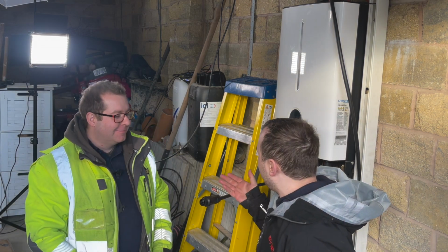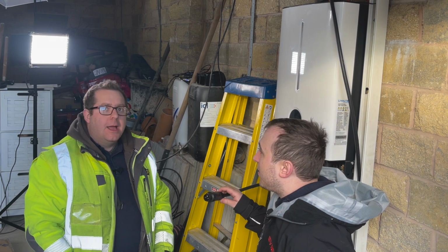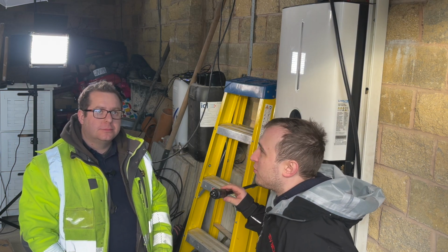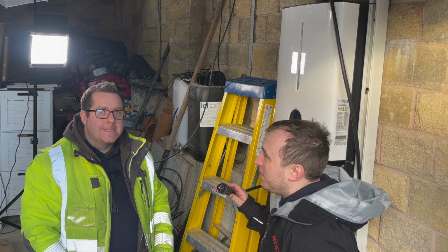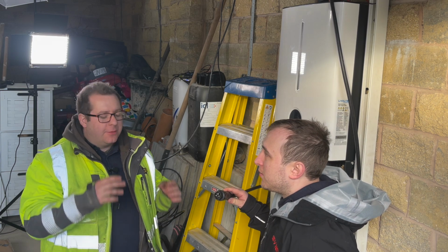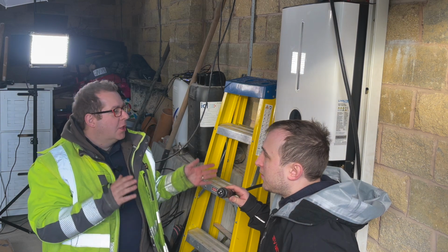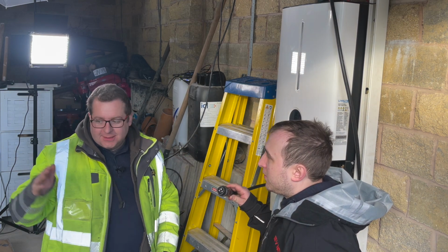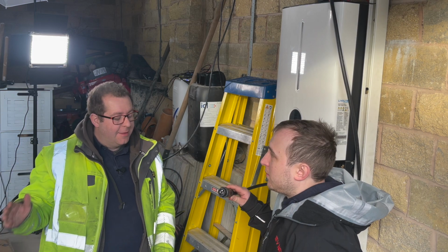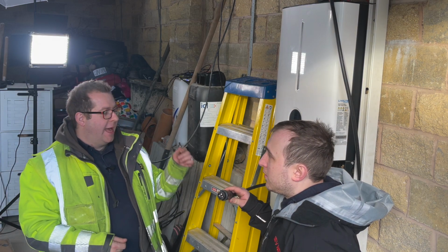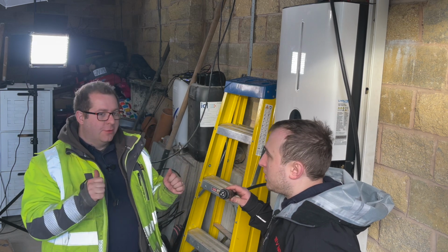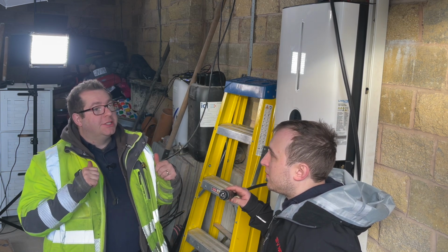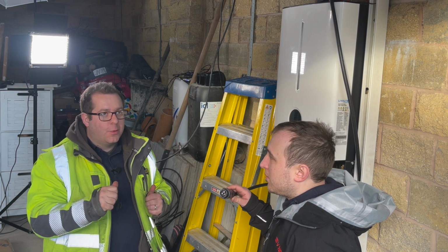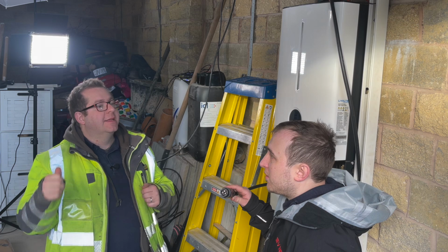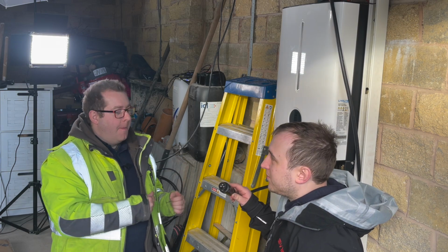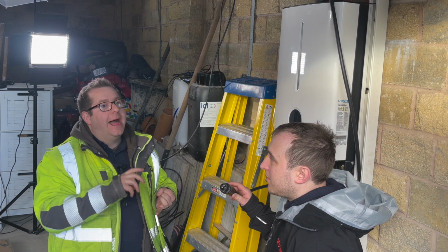But I mean, is it possible to do it legally? Is there a way of doing it so you could run the whole house electric, or is it always going to be on a separate EPS switch, without any kind of gateway? If you wanted to run the whole house off it, and Livoltek acknowledged it was okay, you could potentially wire this into a manual changeover switch that would at the same time automatically disconnect from the grid and connect to the house. That is legal and would work.